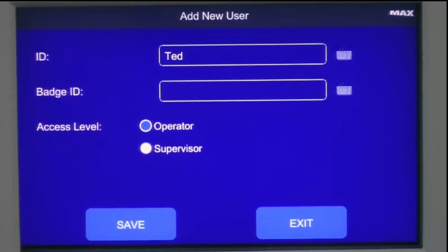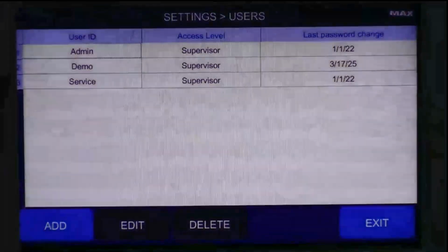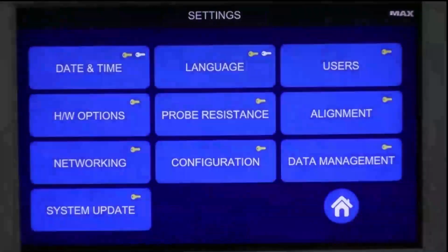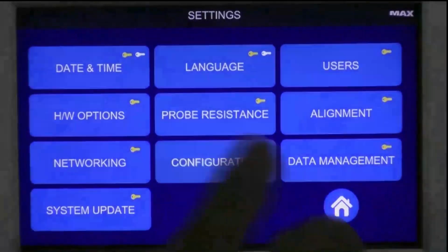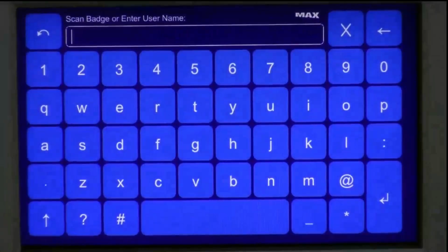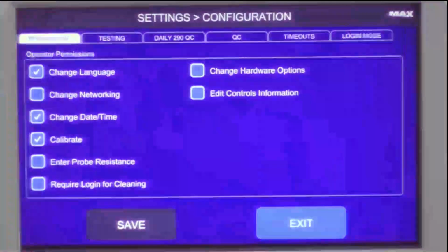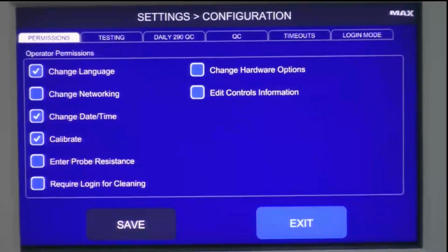So if there's certain things you don't want your operators doing, then you can designate those permissions of these different operator profiles that you would build here in the user menu in this configuration menu. So I'm going to go ahead and scan into here. In the configuration menu here, you can see where you can designate those operator permissions. So if you don't want them changing the language, you can deselect that, or messing with the network, or calibrating, or doing things like probe resistance, or cleaning. You only want supervisors performing these steps. You can restrict those permissions here.